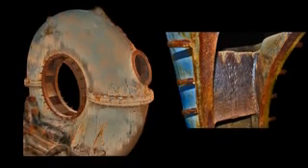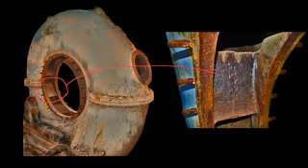This next example is also of a hydroelectric facility. This particular facility dates back to the early 1900s and is now abandoned. This is a picture of a horizontal turbine housing. If we look inside the housing, about here, we can see the results of cavitation and erosion that occurred over the years of service.